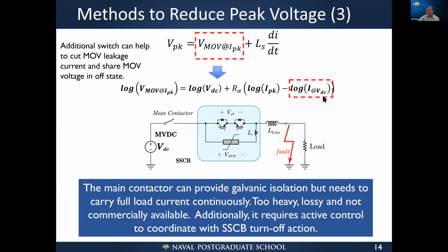Or if you want to increase the leakage current when the MOV is blocking the VDC, the DC link voltage, that can also help. However, we know that the MOV cannot do that, limited by the material. So we need to bring in help for the MOV. One way to do it is to bring in additional switches to cut the MOV's leakage current and share the MOV's voltage in off state. For example, we can add a main contactor here. So when the fault is cleared, we'll open the main contactor to cut the leakage current flowing through the MOV. And this can also share the voltage and provide galvanic isolation, which is good.